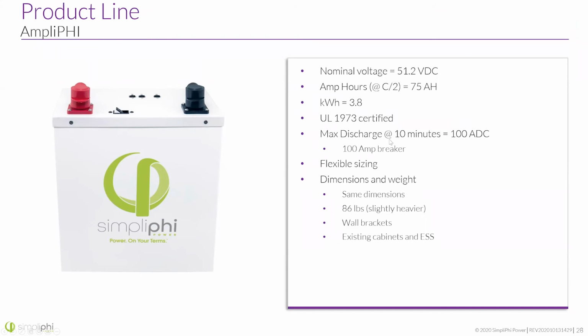Beyond continuous charge, which we talked about as C/2, we also have max discharge, the rating at which the battery can discharge at 10 minutes. This battery can do 100 amps DC at 10 minutes, and every time you add another one you're adding more availability as far as discharge goes, but that's only at the 10-minute mark. The standard Phi battery can do 80 amps, just FYI, for the 48-volt battery.